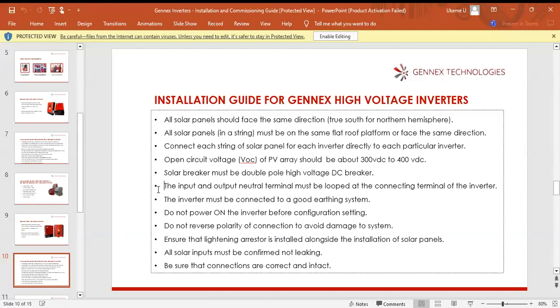Do not power on the inverter before carrying out your configuration. If you want to program the inverter according to the setup, you don't need to power it on. Just use your utility or, if solar is available, switch on only one of the breakers according to a sequence. Do not reverse polarity of connection to avoid damage to the system. Ensure that a lightning arrestor is installed alongside the solar panel installation, which is very important.